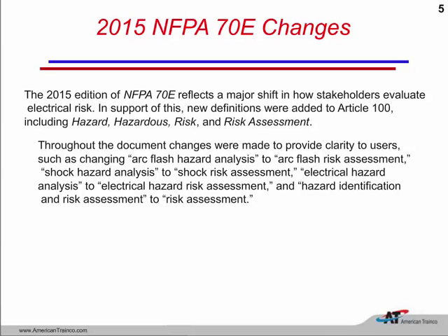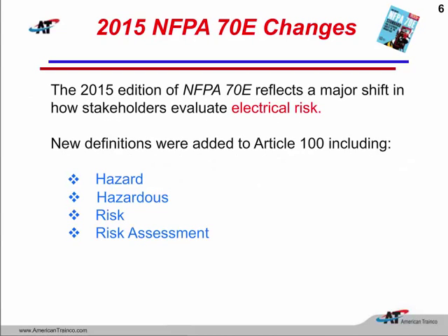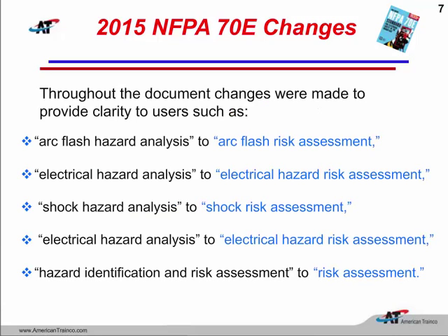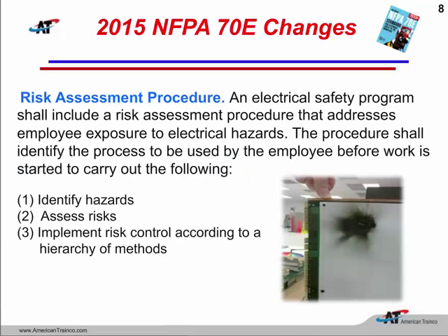But it doesn't matter what the hazard is, we are going to do a risk assessment. They have put a new annex in the back of NFPA 70E to give us some guidance on how to perform these risk assessments, and we'll be talking more about them as this presentation continues. So, some new definitions for sure, especially because of the terminology of risk and risk assessment taking the place of analysis. Some new definitions were added to Article 100, and there were some definitions that were deleted. But all these analysis terms will be going to risk assessment, and there will be a procedure for us to follow with this, and we will go ahead and take a look at that as we continue.